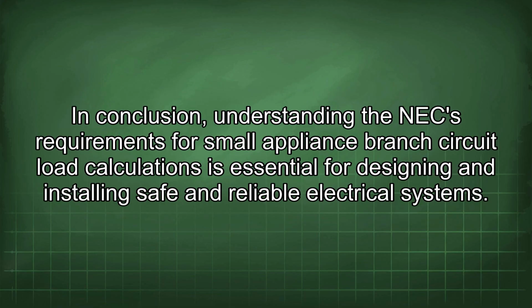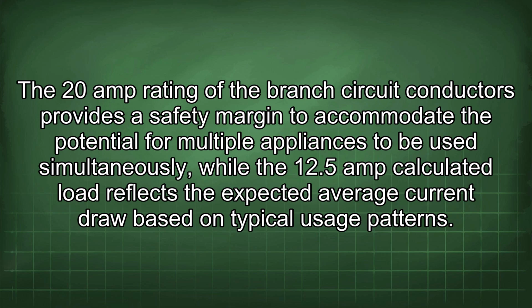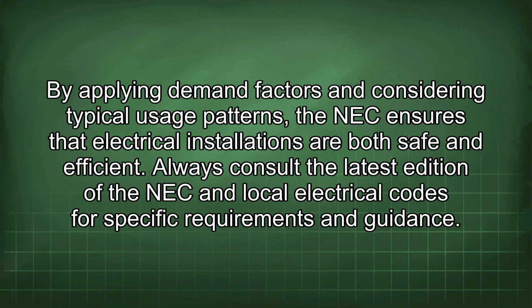In conclusion, understanding the NEC requirements for small appliance branch circuit load calculations is essential for designing and installing safe and reliable electrical systems. The 20 amp rating of the branch circuit conductors provides a safety margin to accommodate the potential for multiple appliances to be used simultaneously, while the 12.5 amp calculated load reflects the expected average current draw based on typical usage patterns. By applying demand factors and considering typical usage patterns, the NEC ensures that electrical installations are both safe and efficient.